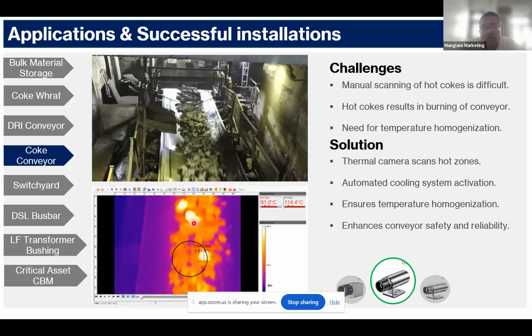You can easily see on those bright red areas that the temperature is higher. Those are at 114 degrees, whereas the other temperature is around 81 degrees. Now, if product is coming at 114 degrees and you have a threshold set up to 150, anything crossing 150 generates an alarm so you can activate your sprinkler system, or at least the user is aware that the product temperature is now at 150 degrees.